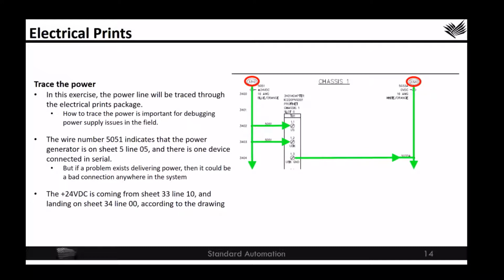So if we look at the drawing on the right, we can see that the wire number 5051 indicates that the power generator is on sheet 5 and line 5, and that there is one device connected in serial. But if a problem exists delivering power, then it could be anywhere in the system. The bad connection could be halfway through the circuit or three-quarters of the way through the circuit. We can't just skip to the power generator and say, well, if the power generator is okay, then everything else is okay. In this instance, we know there's at least one device connected in serial, and there are probably some terminal points connected and used along the way that could have a loose connection. The electrical prints package will tell us where those connection points are.